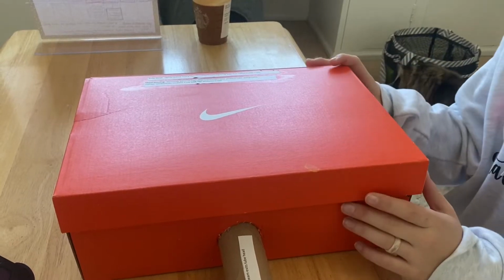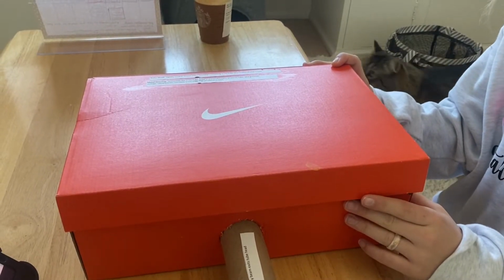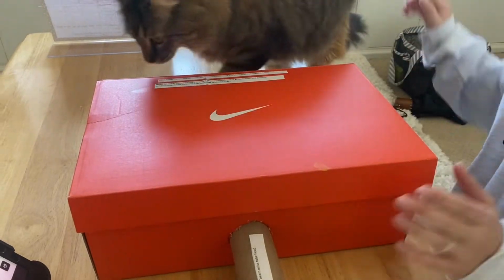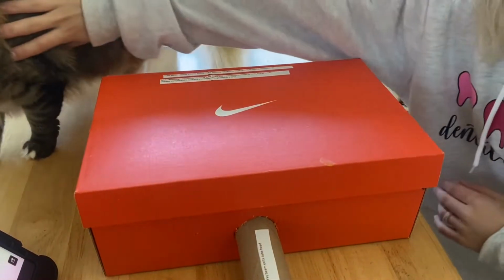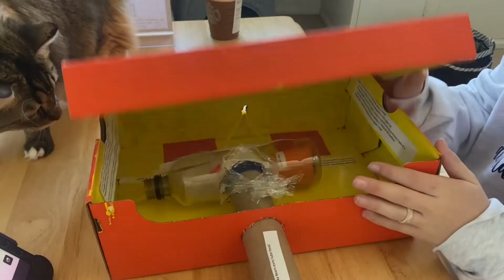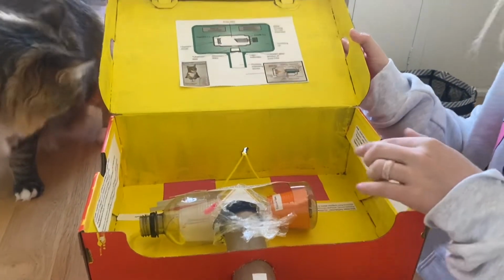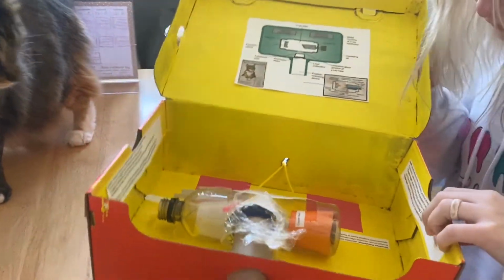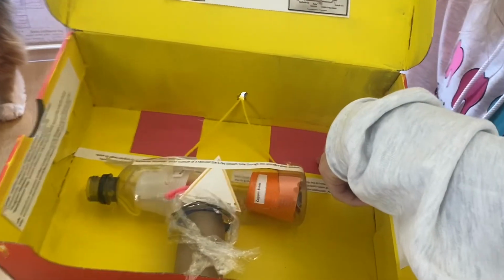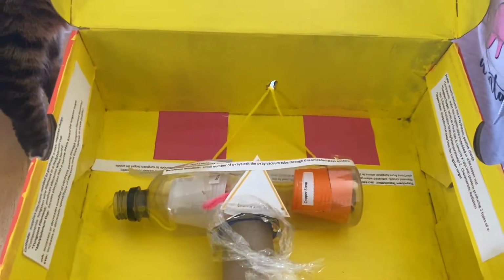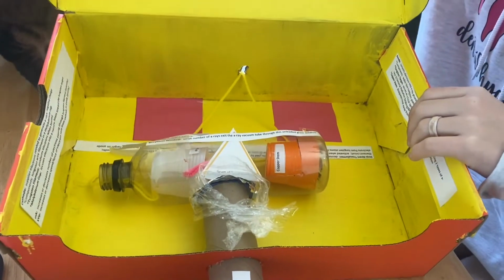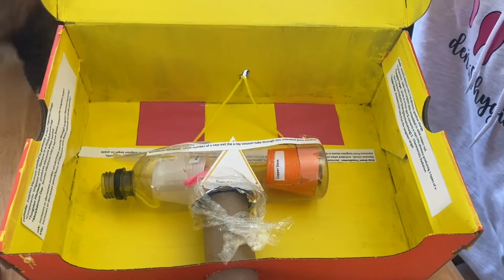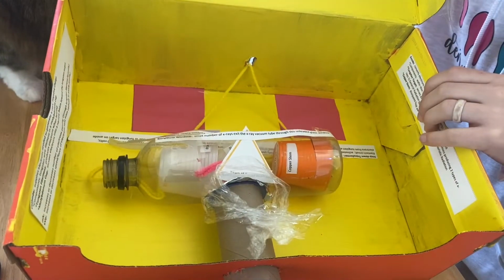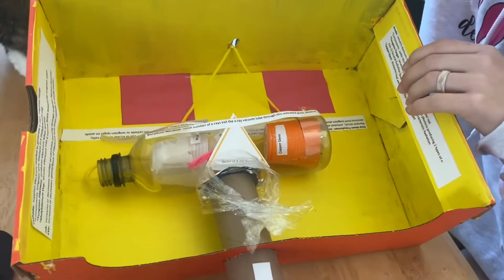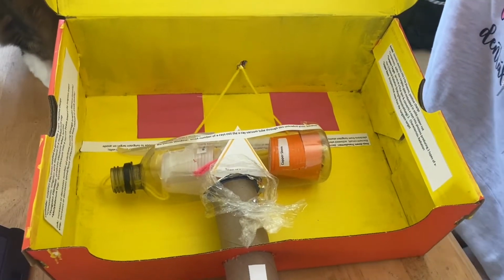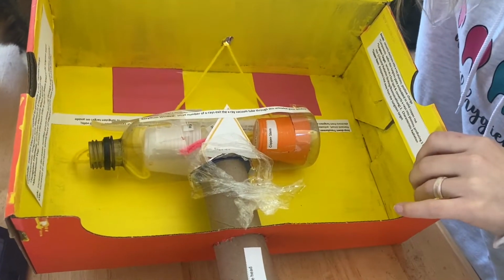Okay, so here's a tube head, which is the metal housing that contains the x-ray tube and that makes the dental x-rays. Let's take a look inside. Here we have the step-down transformer and the step-up transformer. The step-down transformer is what is going to decrease the voltage from incoming volts used by the filament circuit, and the step-up transformer increases the voltage from incoming volts.